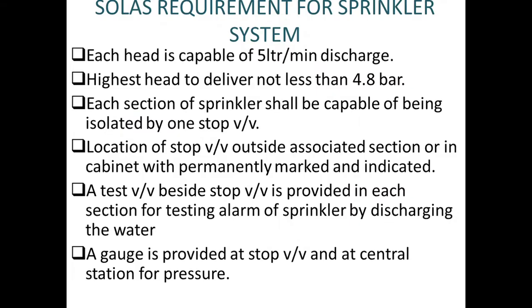Now, the next requirement: each head is capable of 5 liters per minute discharge. I could even find on some websites it was written 100 liters. I won't name them, but still. Now, the highest head must deliver not less than 4.8 bar. When we talk about the tank capacity and the tank pressure, it has to have water as well as air, so that the highest head is able to maintain 4.8 bar. So it has to be designed so, and kept at that optimum pressure.